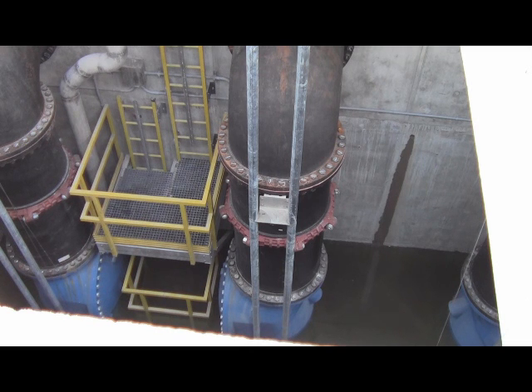These are the pumps, with landings for maintenance and landings in between the two sequences of pumps. The check valves, the big blue ones, stop the water that is always on top, which reduces the back pressure onto the pumps. The pumps are made so that they can slide up the rails and lift right out. A crane picks them up, and the pumps are about 14,000 pounds, so you need a fair size crane, a 90-ton crane, to pick one out.